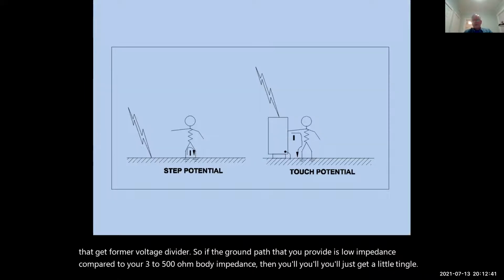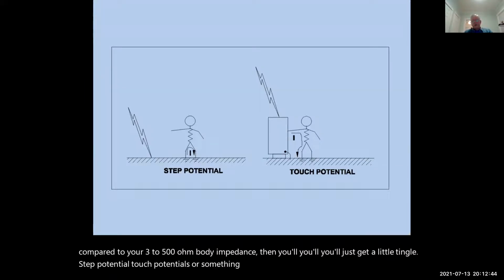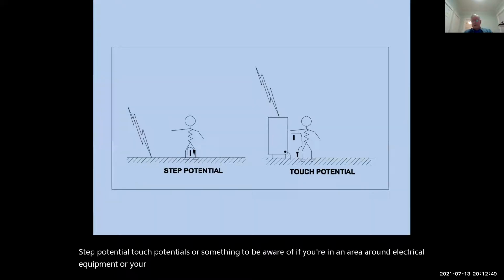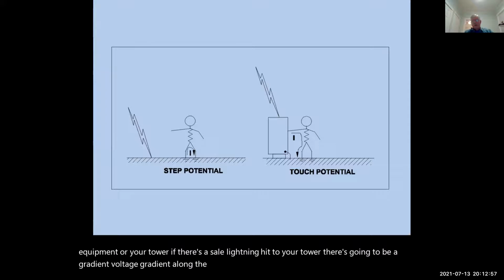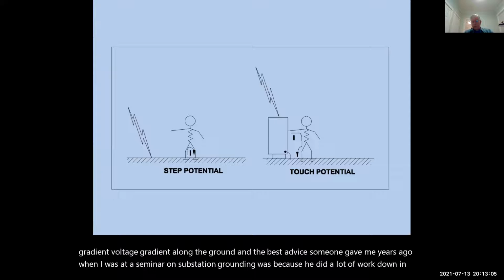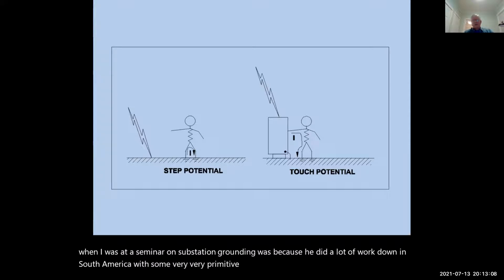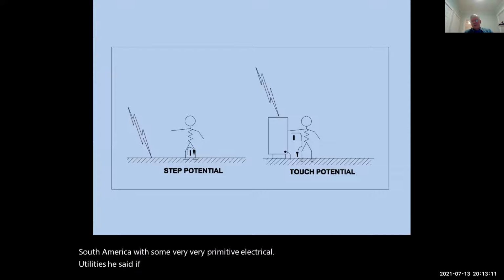Step potential and touch potential are something to be aware of if you're in an area around electrical equipment or your tower. If there's, say, a lightning hit to your tower, there's going to be a voltage gradient along the ground. The best advice someone gave me years ago at a seminar on substation grounding, because he did a lot of work down in South America with some very, very primitive electrical utilities, was: if all of a sudden you find the hair on your arm is standing up, lift one foot and hop away as fast as you can.